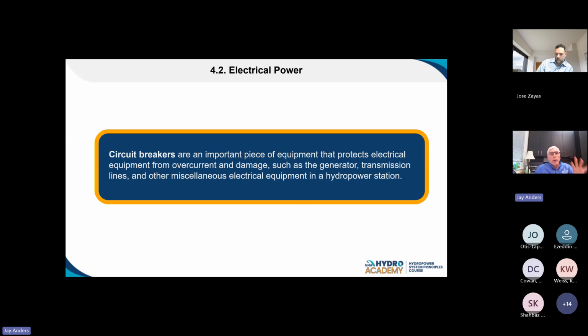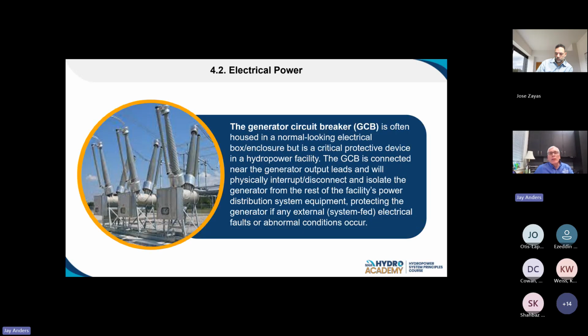And that's what an overcurrent condition could do, an undervoltage condition could do that. There's lots of different things we protect for nowadays. But ultimately, when one of these situations arises that could cause damage to the equipment, we trip the generator breaker, take it offline, the governor grabs hold of it, keeps it from overspeeding. The governor will drive the speed back down to get it to speed, no load, and allows the plant to get into a safe condition.